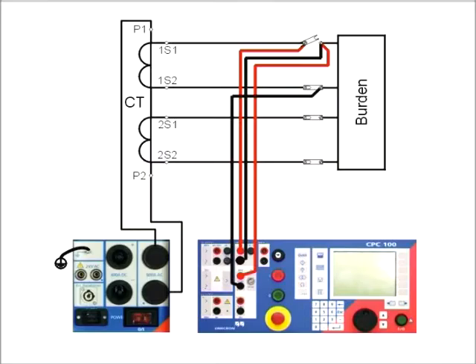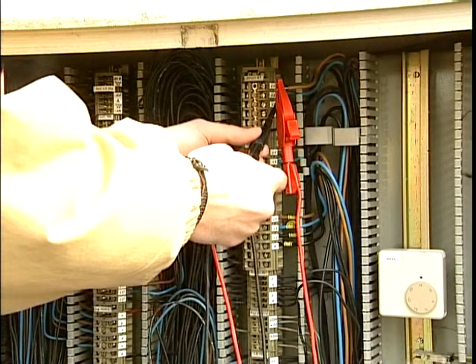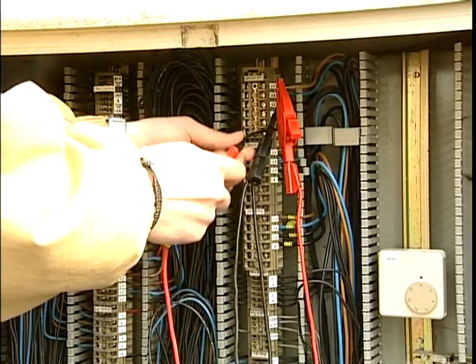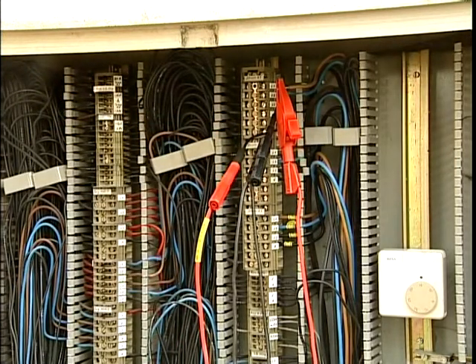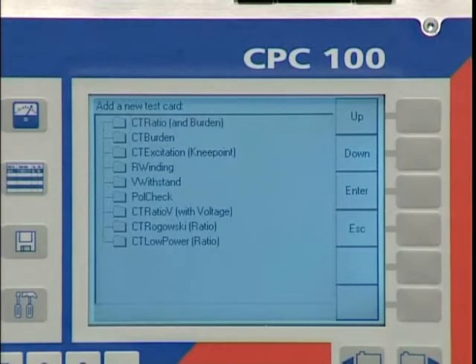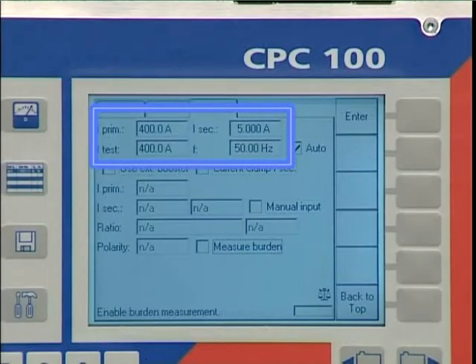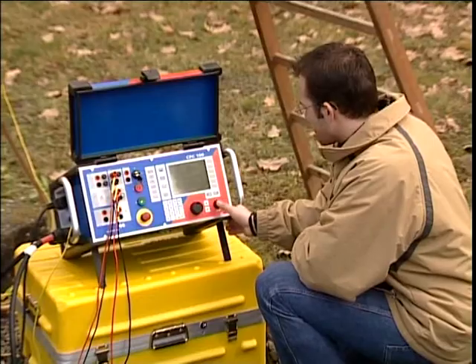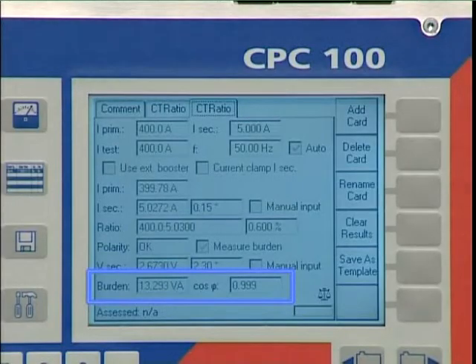For nominal current tests, the burden of the CT can be measured using the same test setup. For this, we take the voltage drop at the burden into account also. The burden is measured as complex impedance. The result is displayed as apparent power in VA with the power factor cosine phi.